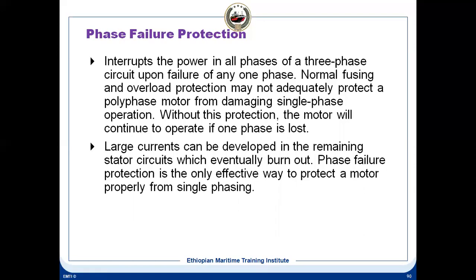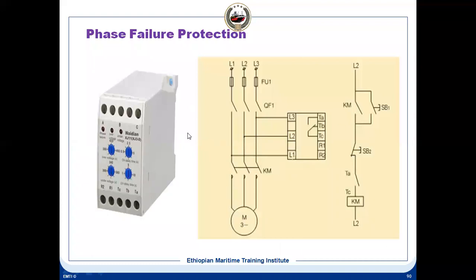Normal fusing and overload protection may not adequately protect a polyphase motor from damaging single phase operation. So here the advantage is that if single phasing takes place, it will trip the motor or starter. Without this protection, the motor will continue to operate if one phase is lost. But with this phase failure protection, it will trip the motor. Hope this diagram is clear to you.